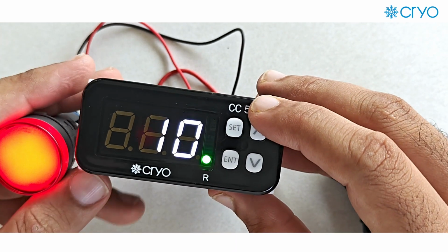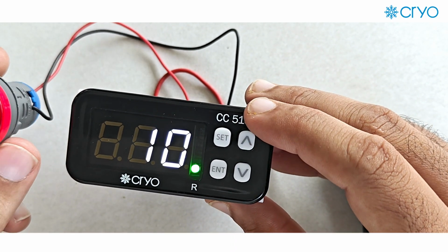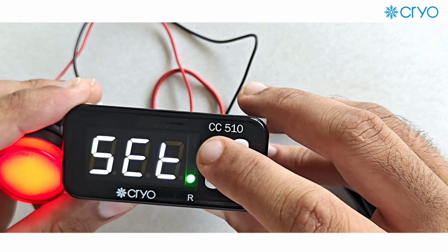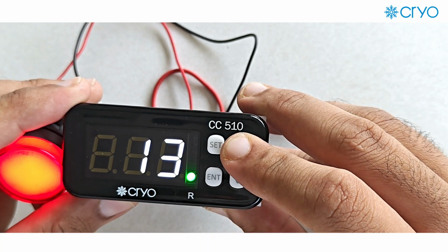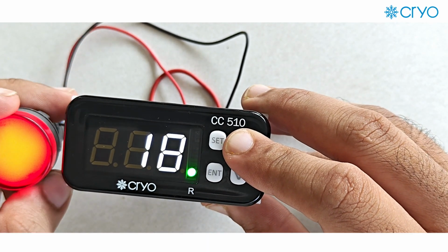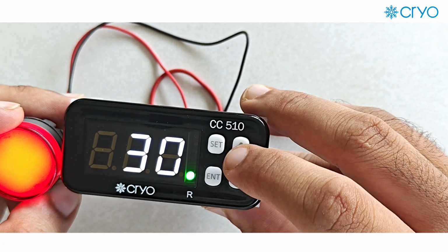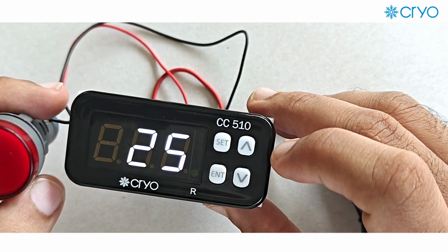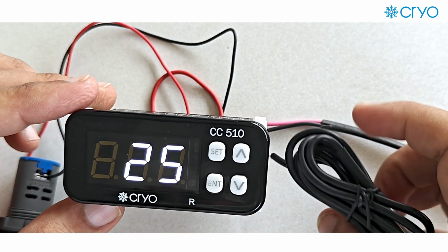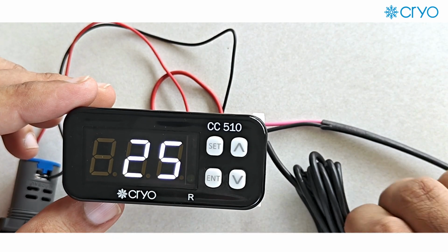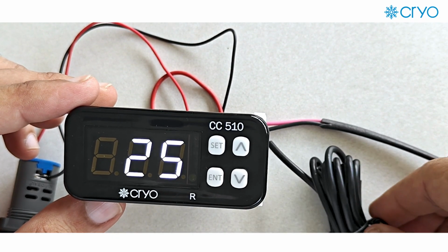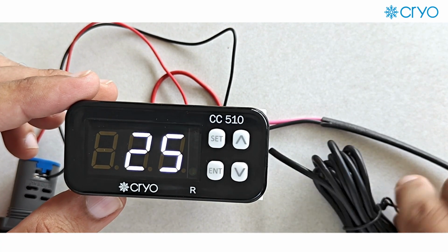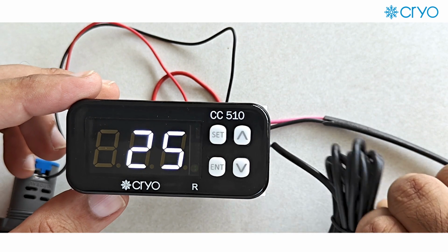As you can see, currently my set point is 10 degrees. In order to achieve 10 degrees Celsius, my relay output is constantly on. So what I'll do in the set point page, if I make it more than 25 degrees, my relay output will get off in that condition. I have made it 28 degrees, so my relay output is off. In the parameter page also, the high set point we have made 30. If I increase the temperature of this sensor, what will happen? Above 30 degrees Celsius, it will show me a high alarm.